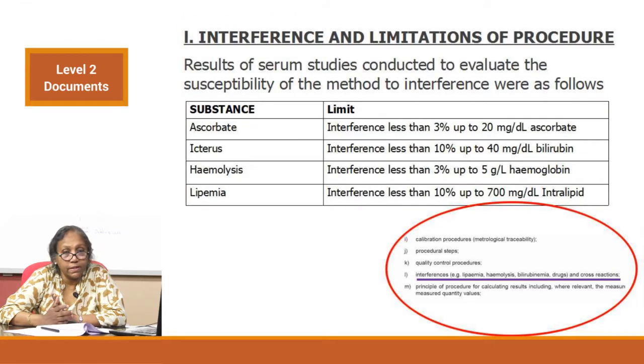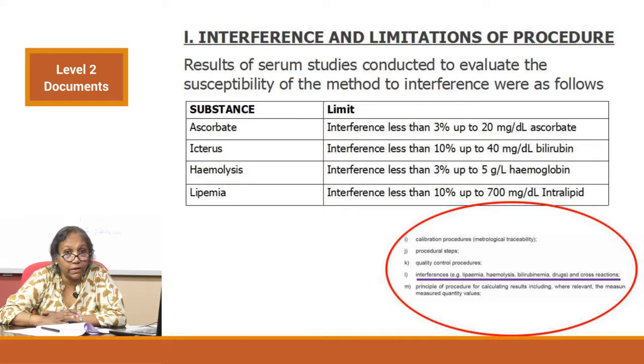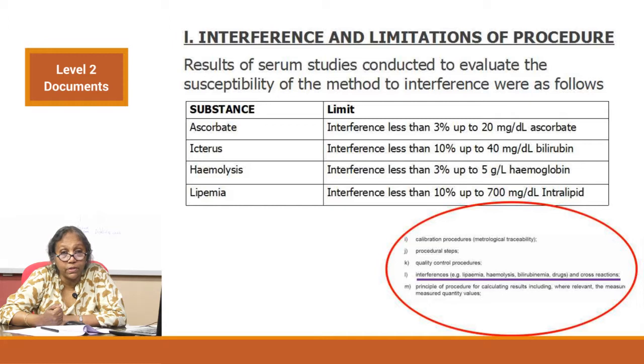Sub-clause L is interferences and limitations — specific to each reagent, given in the kit insert. Make sure you write it down. For glucose, there are four interferences — generally LIH: Lipemia, Icterus, and Hemolysis — plus Ascorbate is also listed. The kit insert gives the cutoffs for all these kinds of interferences, so the technician will know if a very high bilirubin sample is causing interference on the glucose result.